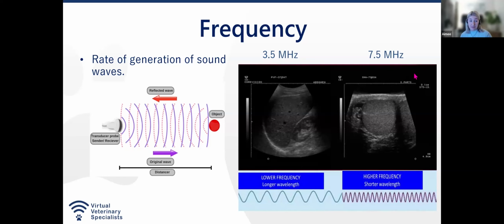So there's always a trade-off, okay? So think of it as low frequency, you get more depth, but a lower resolution. High frequency, high resolution, but lower penetration, okay? So your big dogs, low frequency, your little tiny kitty cats, high frequency, okay? And obviously we will probably need to adjust this through the scan. So if we're looking at the abdomen, we're probably going to need a lower frequency than when we're looking at a kidney because of the depth of what we're going to need to be traveling.